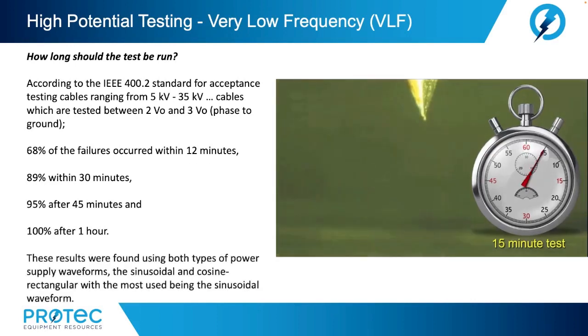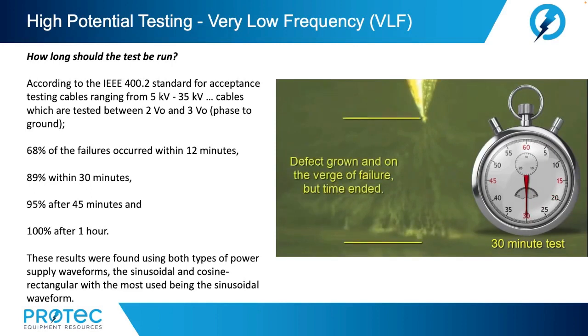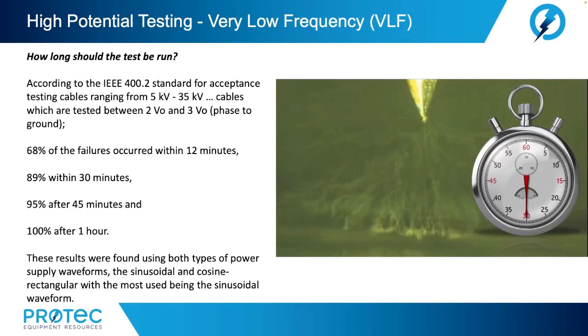These results were found using both types of power supply waveforms, the sinusoidal and the cosine rectangular, with the most used being the sinusoidal waveform type. And here in the illustration, we show the channels growing during the test voltage. As we see, it takes time in some situations to grow the defect to point of failure.